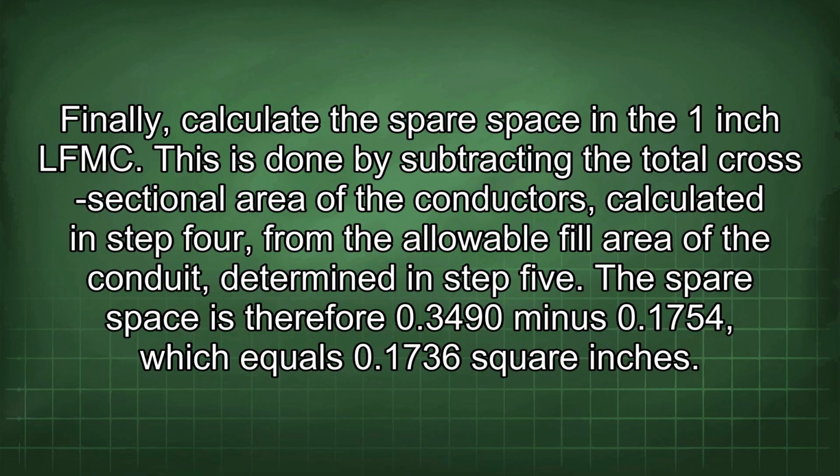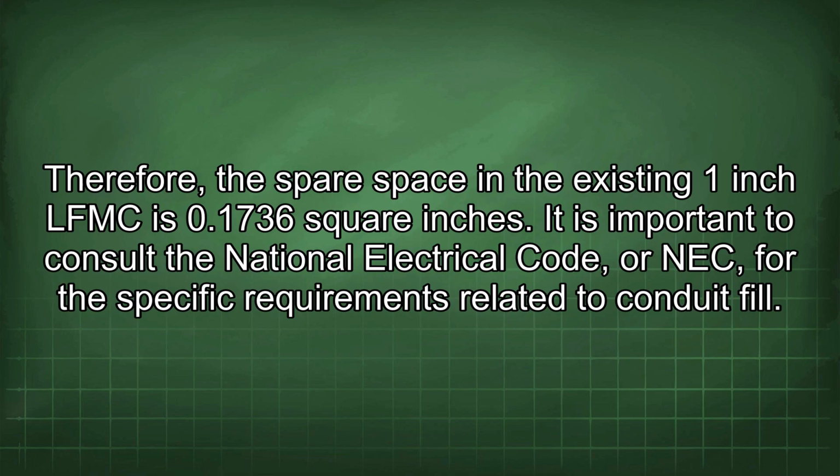The spare space is therefore 0.3490 minus 0.1754, which equals 0.1736 square inches. Therefore, the spare space in the existing 1-inch LFMC is 0.1736 square inches.